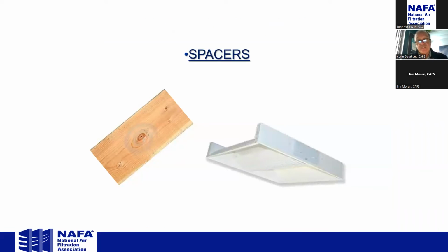Okay. Spacers. Unfortunate that we have to use spacers, but it seems that with side access tracking with filters in an air handling system, for whatever reason, the math never seems to work out, and there are always 2 or 3 or 4 inches left over at the end. We suggest spacers do work just to fill that void. Put them in the far end of the system so that they aren't removed and lost at filter replacement time. And again, just keep your eye on them and make sure that they're still functionally sound as time goes on. Again, a very inexpensive way just to seal that filter bank, make sure the air goes through the filter, not around it.